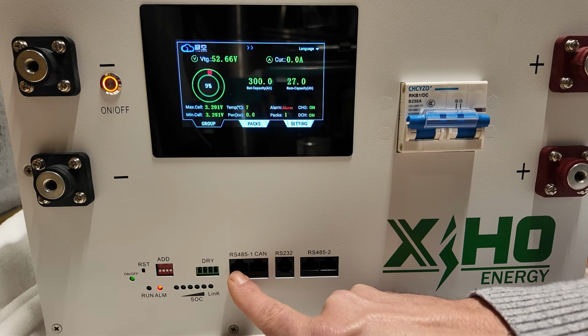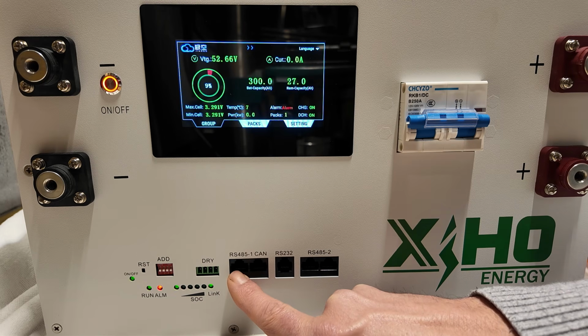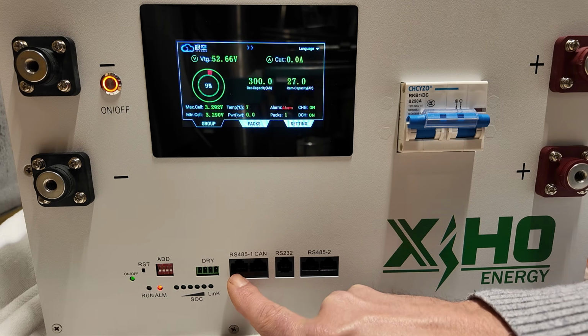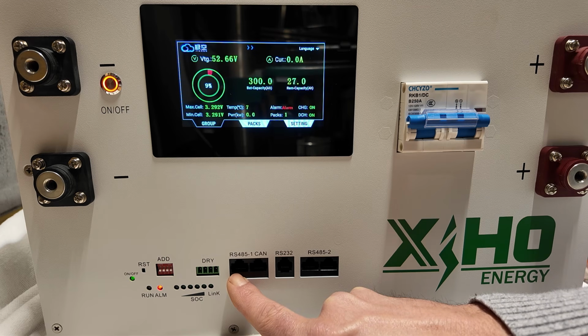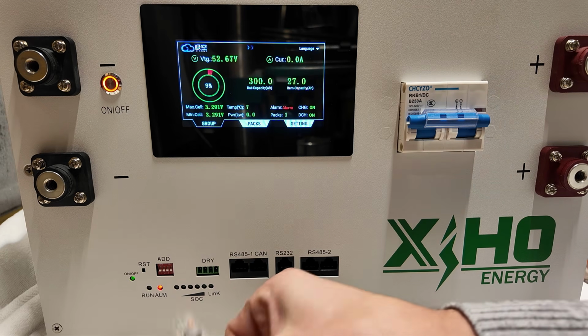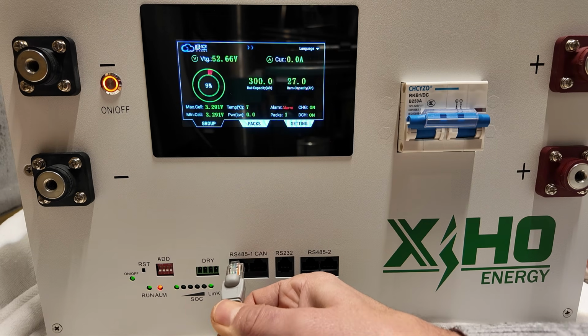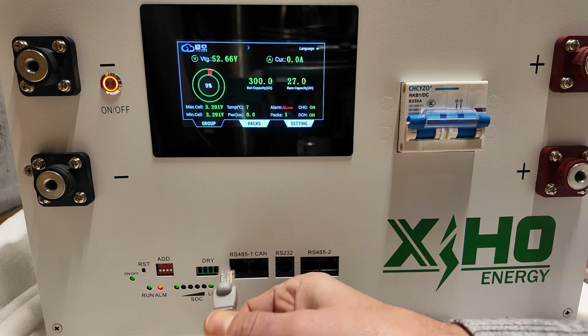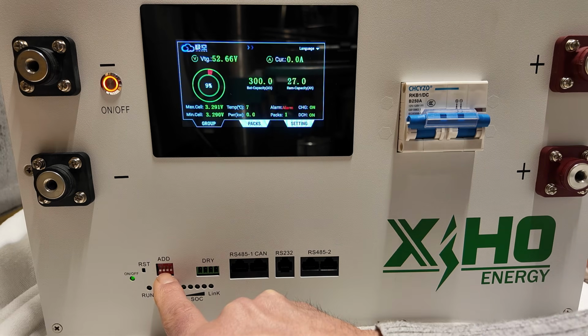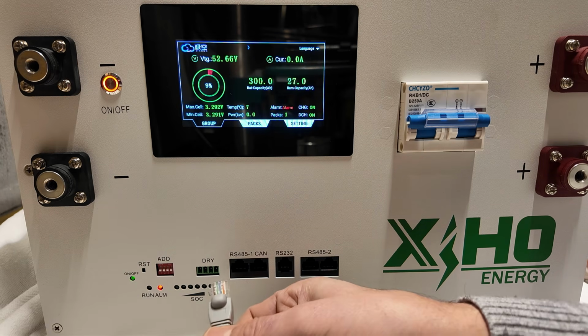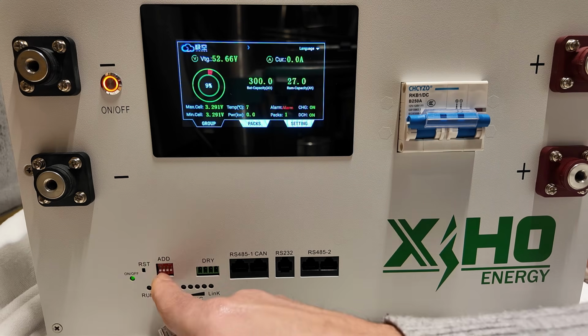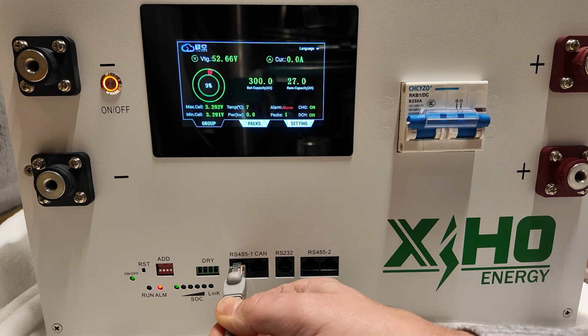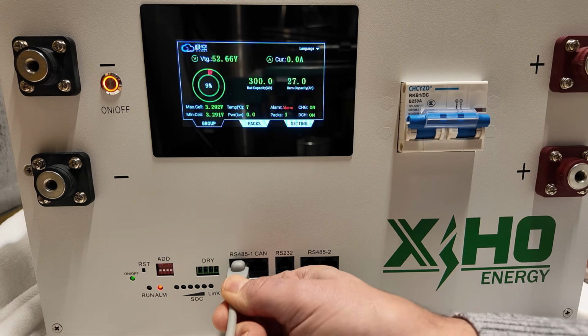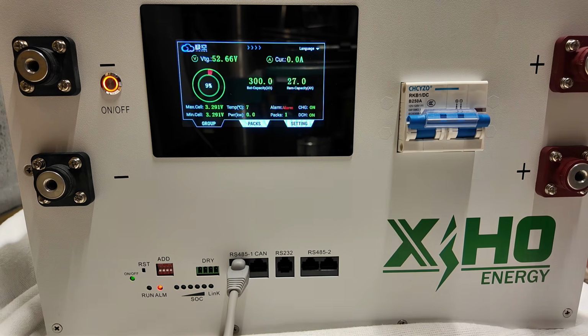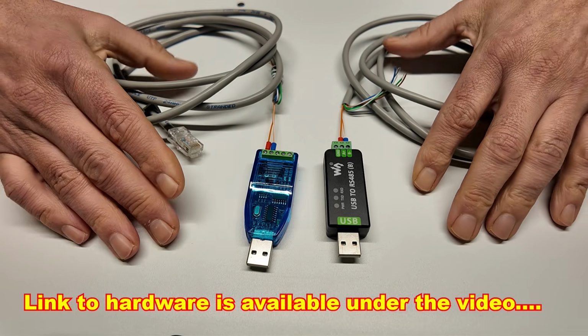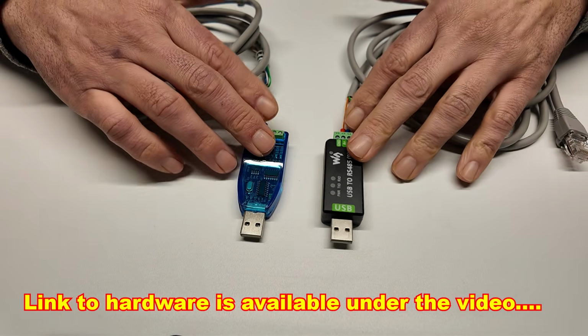At the left we have another RS-485 and a CAN port. This is to connect your inverter or other hardware from your Victron ecosystem. Important, if you use the computer, you have to use this port, the most left port. Set all your dip switches to 0. Not really needed, but I have only one system, so I set it to 0 and connect it. Like this.